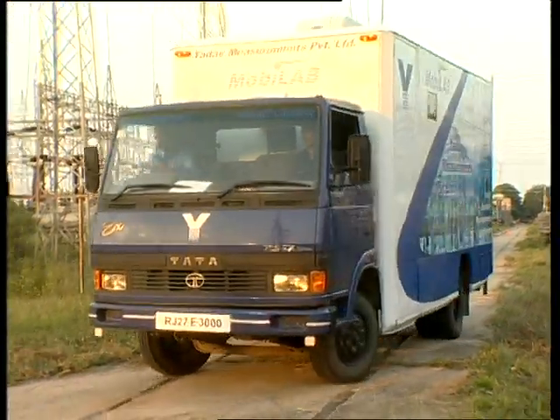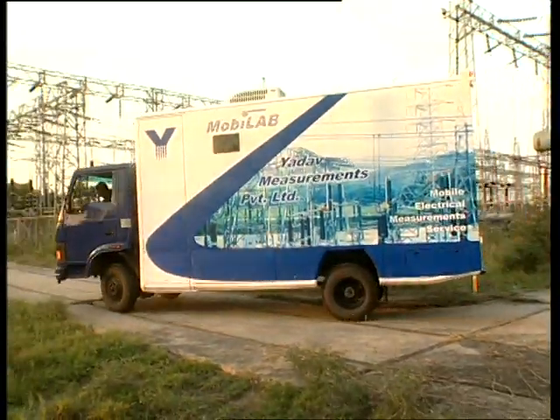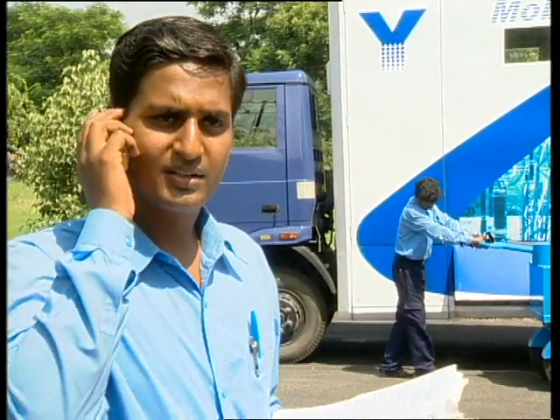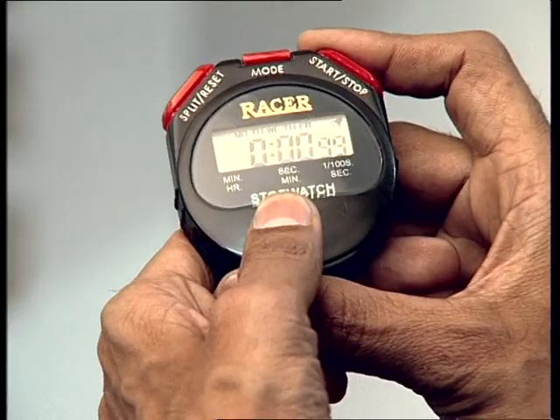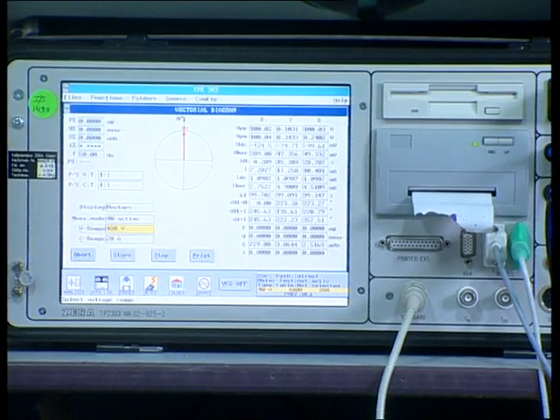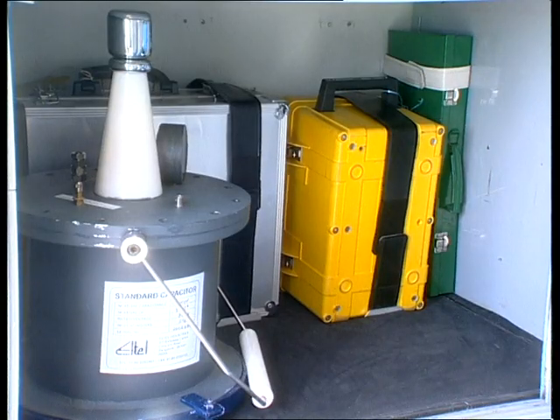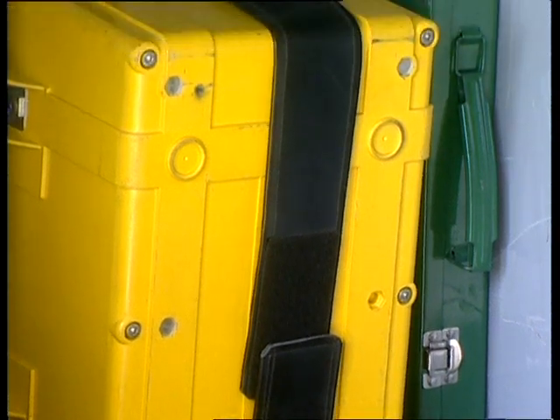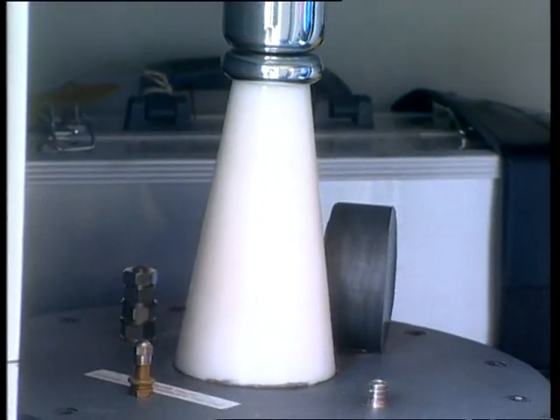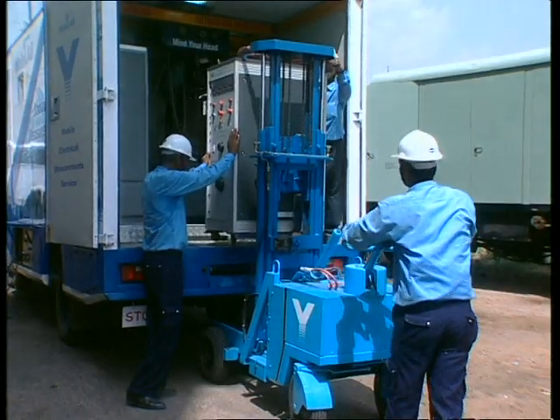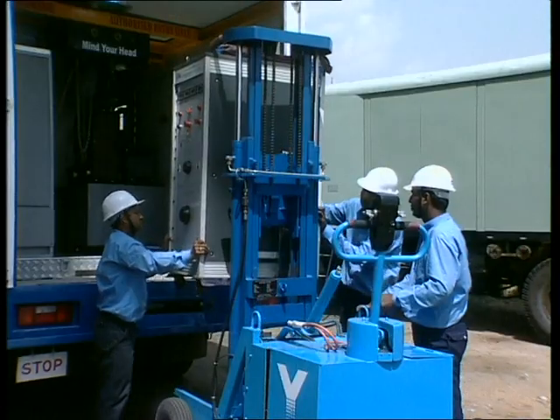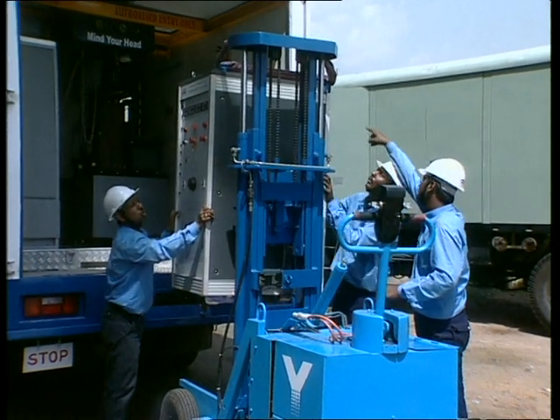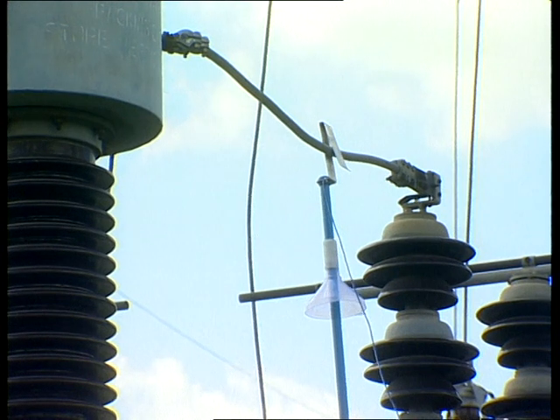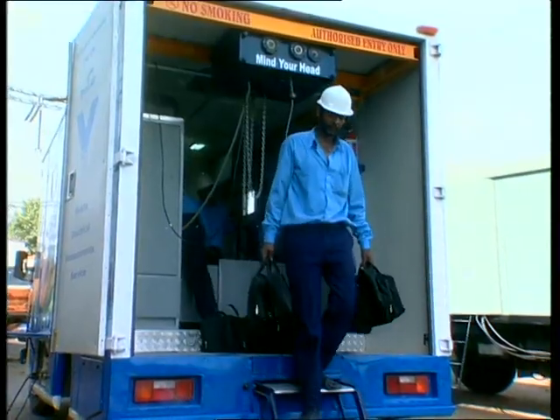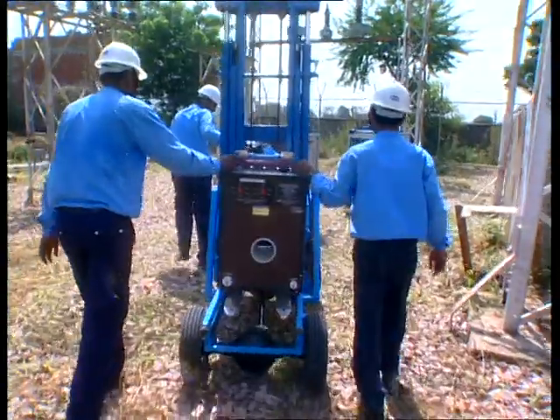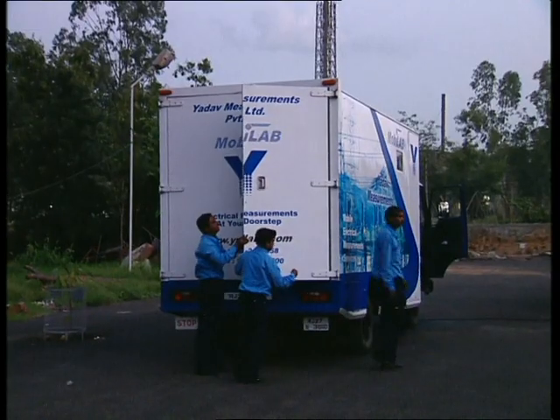MOBILAB represents an ideal solution for better substation measurements. It brings together the four aspects critical to its endeavor: accuracy, speed, quality and safety. Accuracy, the key to all measurements. MOBILAB is equipped with instruments that are several folds more accurate than the best substation instruments. Meticulous care in operation and maintenance in the hands of a competent crew ensures repeatable and reproducible measurement accuracy. Speed, the essence of working in live substations with minimum work disruption. The MOBILAB crew practice procedures designed for quick setup, accurate testing and rapid wind-up.